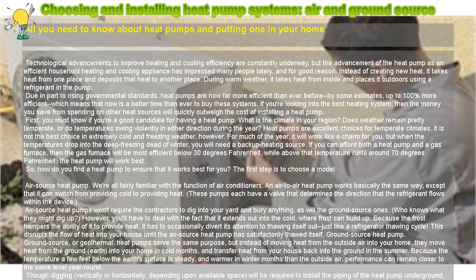If using an air source heat pump, the contractor should install it ideally where it won't be near your bedroom or near neighbors. Be sure the installation is made in the proper location relative to pre-existing furnaces. The outside portion of the air source heat pump should be on a platform to promote drainage and ensure that it won't be snowed in. A windy location should be avoided when you install a heat pump.